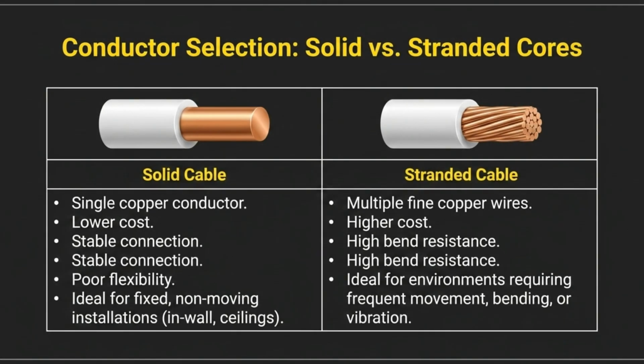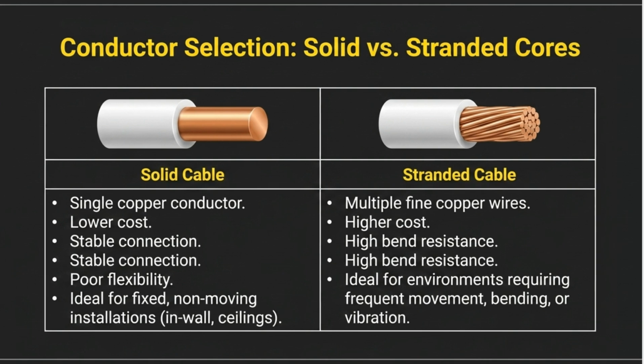Conductor selection involves choosing between solid and stranded cores. Solid cables are lower cost with stable connections, but have poor flexibility. Stranded cables, made of multiple fine wires, cost more but offer high bend resistance, ideal for moving installations.